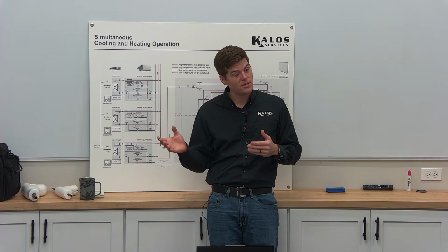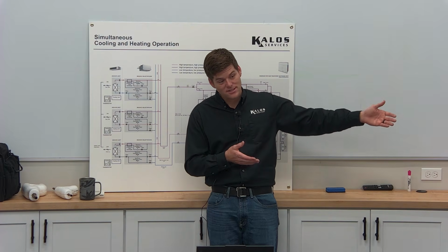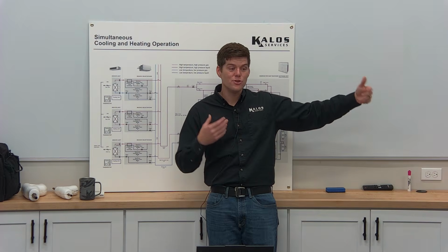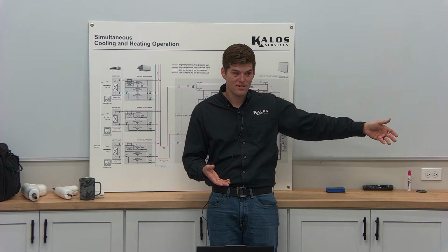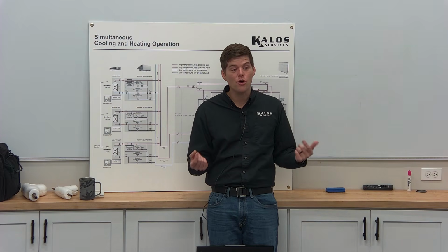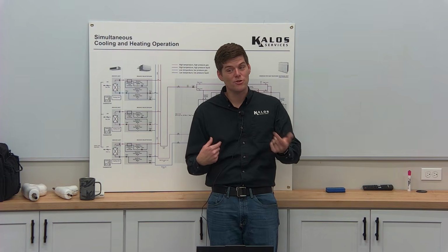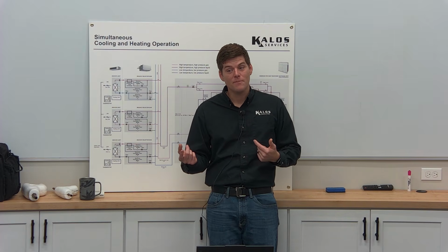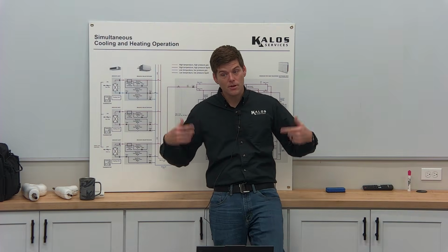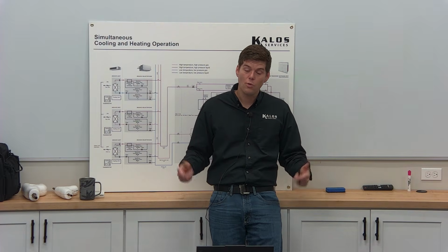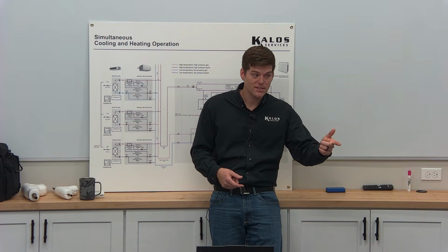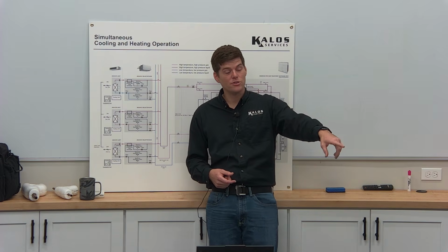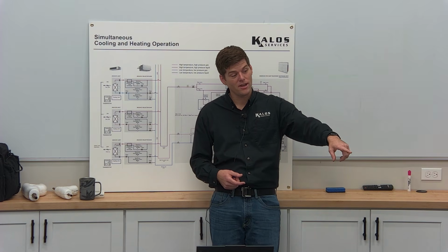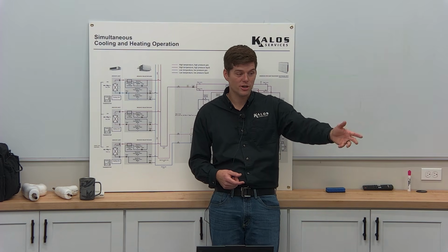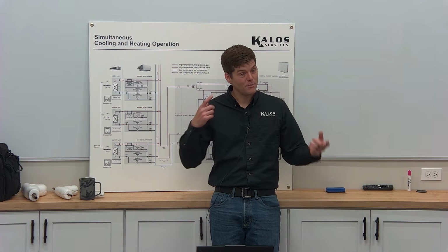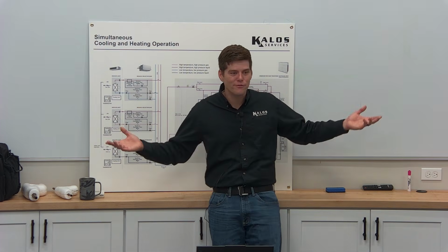The outdoor unit is talking to the indoor unit constantly, somewhere upwards of 200 communications per second between everybody. It knows who's on first, who's on second, who's on third, who needs what. And it uses a PID loop, right, to determine what your needs are going to be. It says you're satisfied, but I see that your temperature has been creeping up by 1 degree every 15 minutes, and so you're eventually going to call here probably in the next 15 minutes. And it predicts that.